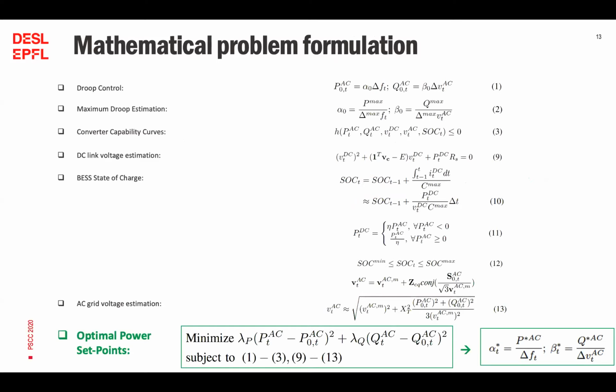So if the initial set point falls inside the corresponding capability region, then the two final set points P and Q will be the same as those calculated initially. Otherwise, the closest feasible point will be selected, calculated, and then sent to the battery. In this way, we guarantee the continuity of the service provision. And just notice that we included two weight factors, lambda P and lambda Q, that are basically used to prioritize one service over the other, thus the provision of active power over reactive power or vice versa.